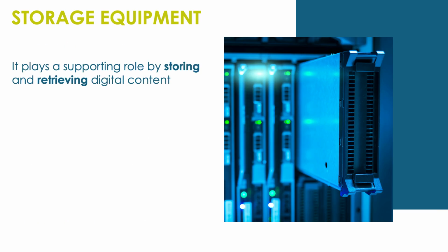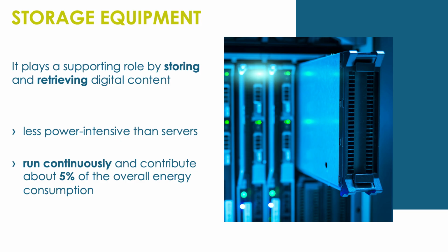Storage equipment plays a supporting role by storing and retrieving digital content. Although less power-intensive than servers, storage systems run continuously and contribute about 5% of the overall energy consumption. The energy demand from this component varies depending on data volume, backup frequency, and type of storage architecture.